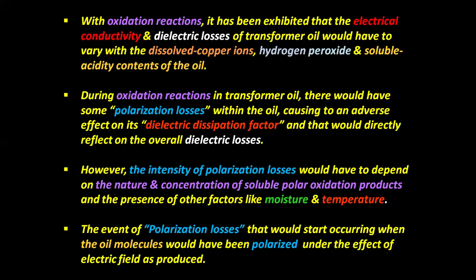With oxidation reactions, it has been shown that the electrical conductivity and dielectric losses of transformer oil vary with the dissolved copper ions, hydrogen peroxide, and soluble acidity contents of the oil. During oxidation reactions, there are polarization losses within the oil, causing an adverse effect on its dielectric dissipation factor. And that directly reflects on the overall dielectric losses. However, the intensity of polarization losses depends on the concentration of soluble polar oxidation products and the presence of other factors like moisture and, obviously, temperature.